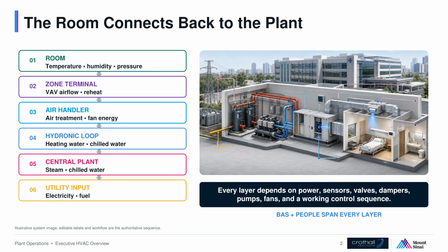Now multiply that chain across roughly 5.5 million square feet, about 15 buildings, more than 40 closed hydronic systems, hundreds of air handling systems, thousands of variable air volume terminals, and thousands of building automation points. The plant includes 6 boilers, 11 chillers, 19 emergency generators, and many shared dependencies. Annual campus utility cost is about $43 to $44 million, roughly $39 million for electricity, $3 million for natural gas, and $1 to $2 million for fuel oil. Those are total campus utilities, not an HVAC-only allocation, and electricity is close to 90% of the total.